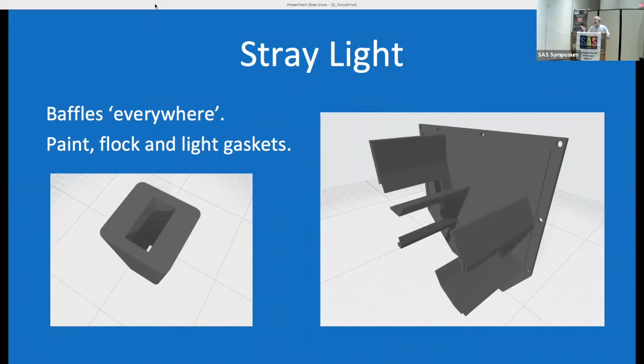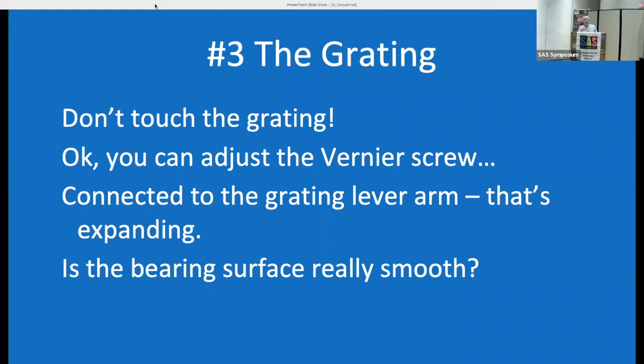Then there's a grating. Don't touch the grating. Well, you've got to touch the grating if you want to select the wavelength, and usually the way it's done is with a vernier, and you adjust the vernier gauge and it pushes on an actuator arm, a lever, and that turns the grating. And they both have different expansion coefficients. So whatever you're going to do, there's going to be movement in that grating, even for commercial spectrographs. So we looked at this and we said, is the bearing really smooth? Can we improve this?